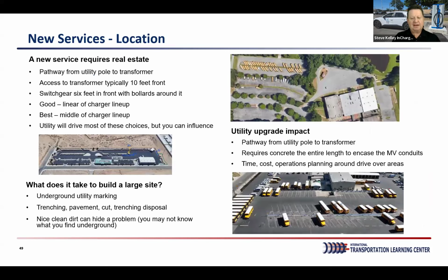Many times when we're rolling out 5 or more buses, sometimes higher, we need to put in new service, meaning additional power on site from the utility to power the larger fleet. Typically a utility will look at where the current power comes in and where they want to put the transformer, and then it's the school's choice of how to build their system around that. Each utility is different, they all have various rules, some will pay for that infrastructure and some won't. Having a good design for building that in the right location is critical.